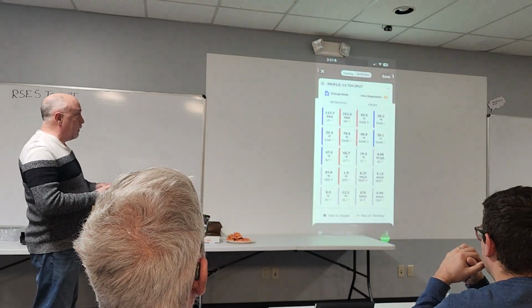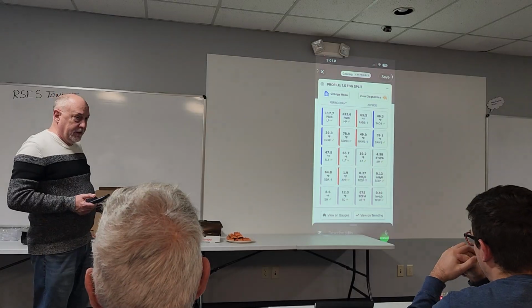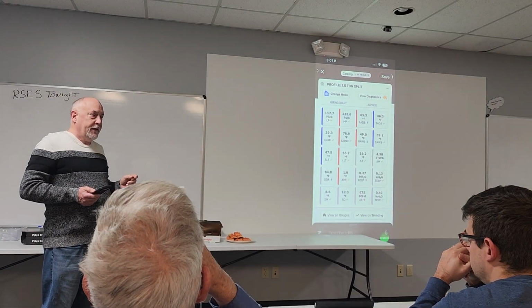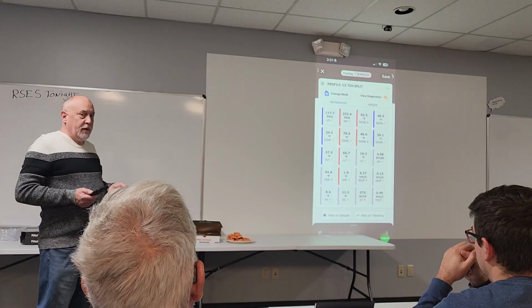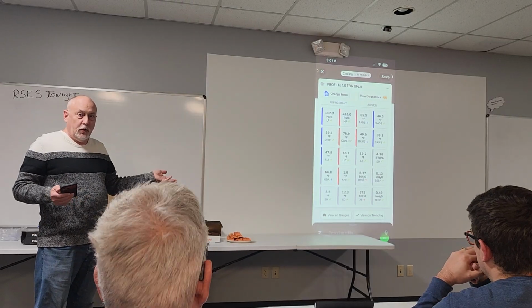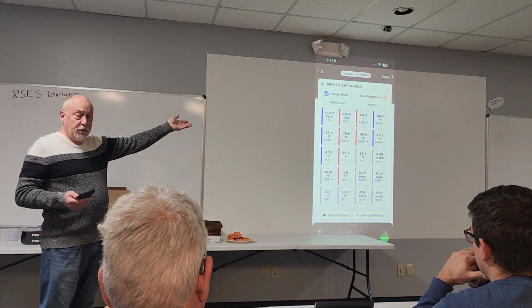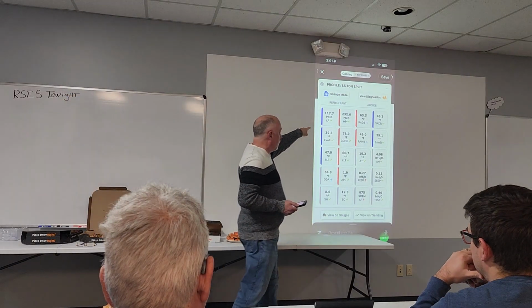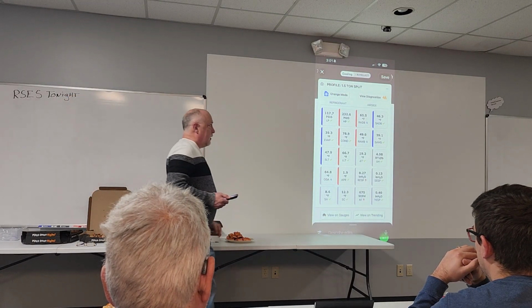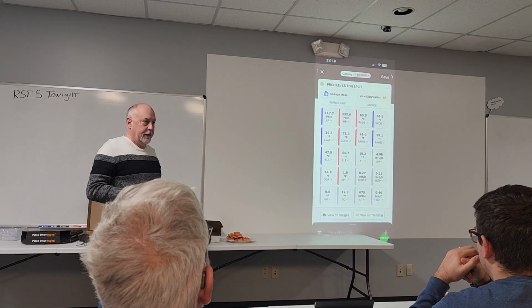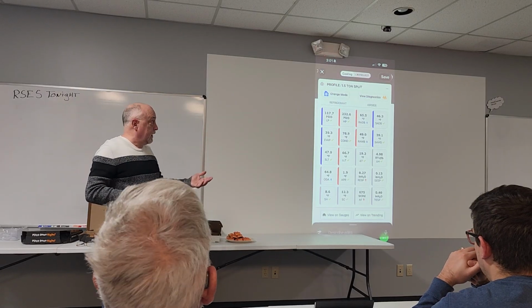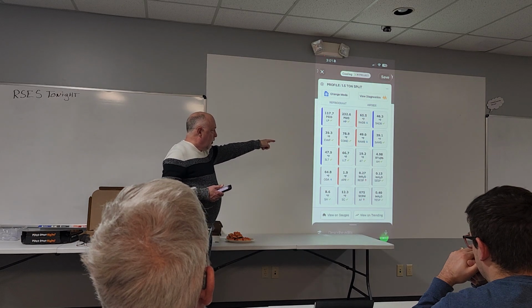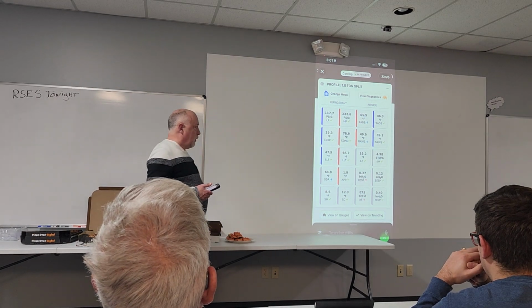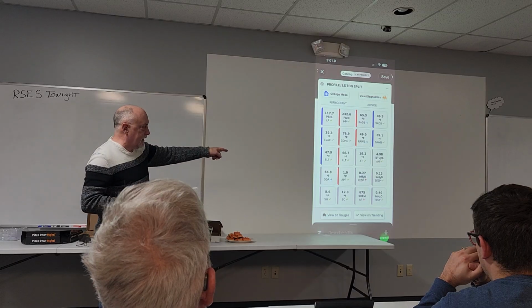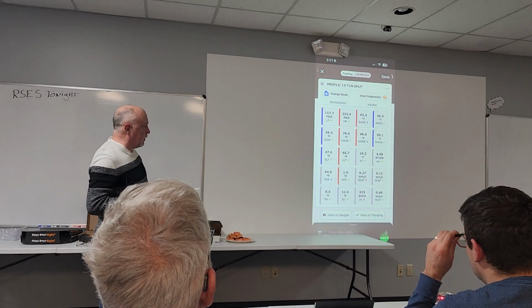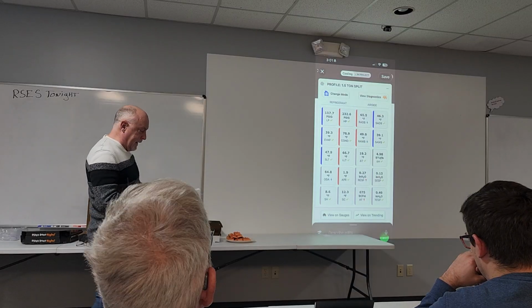When we went up to the top here, we provided it all measurement information. So I'm not telling it, if I started off and said, yeah, my suction pressure looks low, my head pressure looks low, right? Because it's cold outside. The software has already determined what all the target pressures should be. That's what these check marks are. So everything with a check mark means it's in range. So return air dry bulb at 65, that's a low temperature for running air conditioning. The software figured that out already, right? Same thing with the return air wet bulb. Static pressure in the return air static is 0.27. That's a little bit high for return air static because we got a restricted filter. Our airflow is a little bit high. Outdoor air temperature is a little bit low to run that.